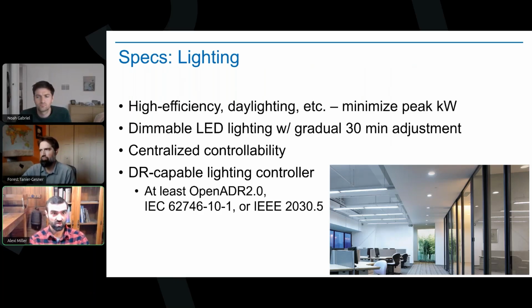California actually has code requirements around demand responsive lighting in commercial buildings. But a couple of key things that we recommend is to have some kind of a central demand response capable lighting controller, again, with those open standard capabilities to make sure it's interoperable and it can take a signal. And it's really ideal to be able to dim this stuff so that it's not really obvious to the people in the building. We all notice when the lights flicker or dim, so having the ability to slowly make the adjustments, ideally, it's imperceptible. The power demand is saved. We adjust lighting for a limited time, and then it comes back up. So that's the general best practice that I would recommend on that.